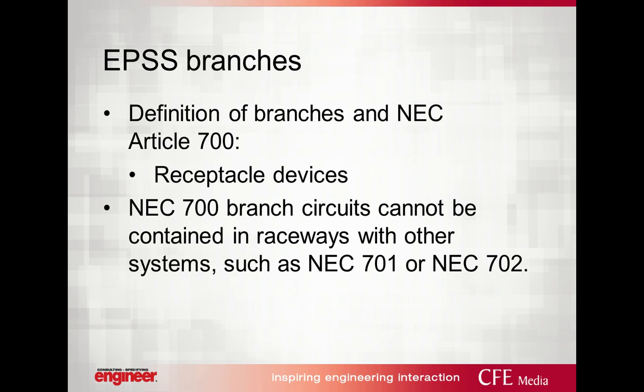The other item I wanted to discuss was branch circuits being contained in a raceway with other systems. You cannot put emergency life safety under Article 700 in conduit or raceways or wireways within any other circuitry that's in the building. So if it's Article 701, you can't put it in it. If it's standard power, you can't put it in it. UPS power, unless that UPS power is deemed for life safety, can't be put in it.